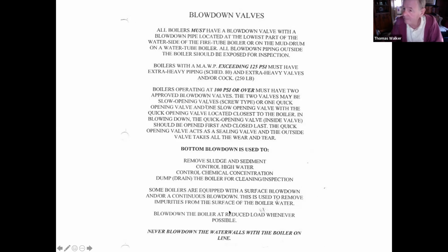Other than that, they tell you to never blow down the water walls on a water tube boiler while there's a fire in the boiler. But the one thing that all inspectors love to hear, you're never, ever going to walk away once the blowdown valves are open. You're not going to answer the phone. You hear the microwave ding, you're not going to walk away. Your favorite show is coming on, you're not going to walk away from an open blowdown valve.